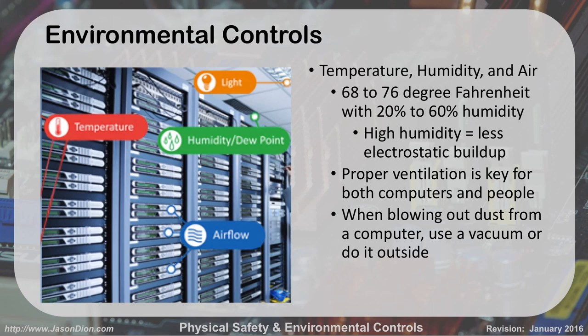Environmental controls. Our server room environments have environmental control sensors all over them. We want to make sure that we have temperature, humidity, and airflow set properly. For us, temperature should be between 68 and 76 degrees Fahrenheit, with about 20 to 60% humidity.